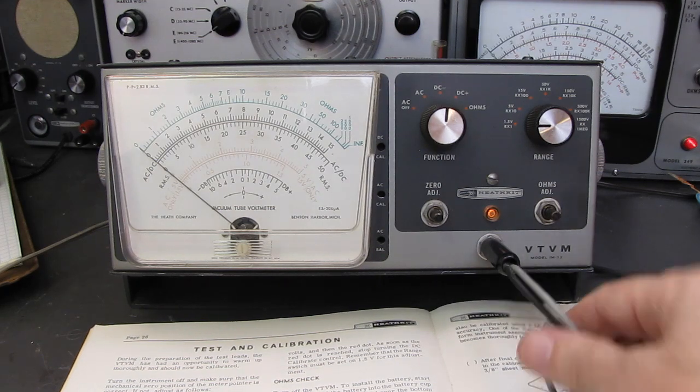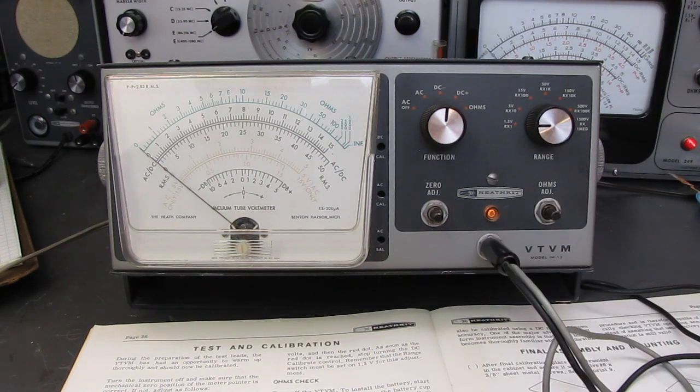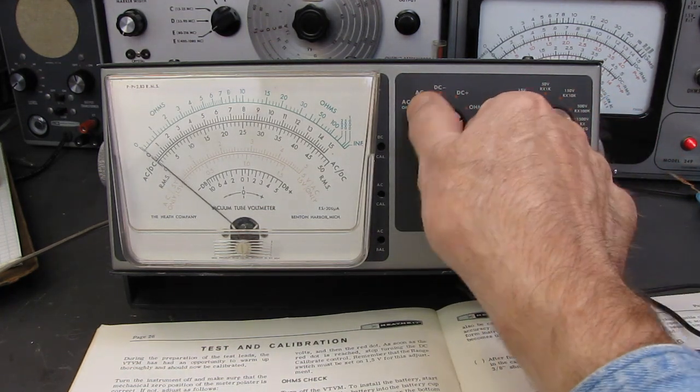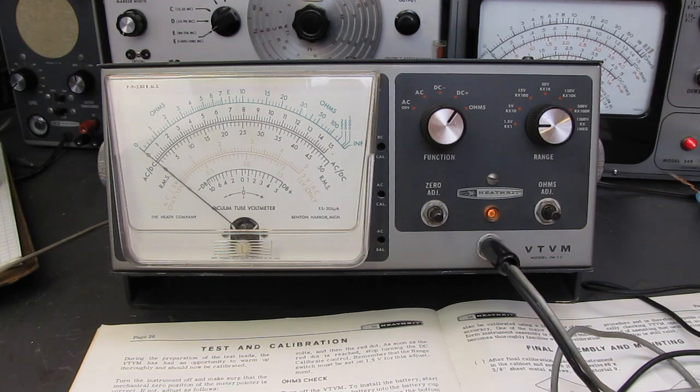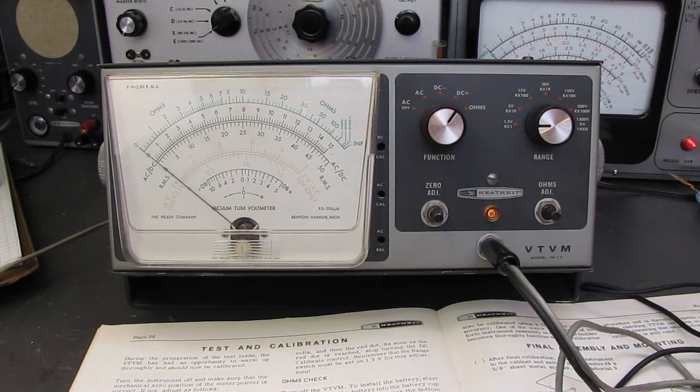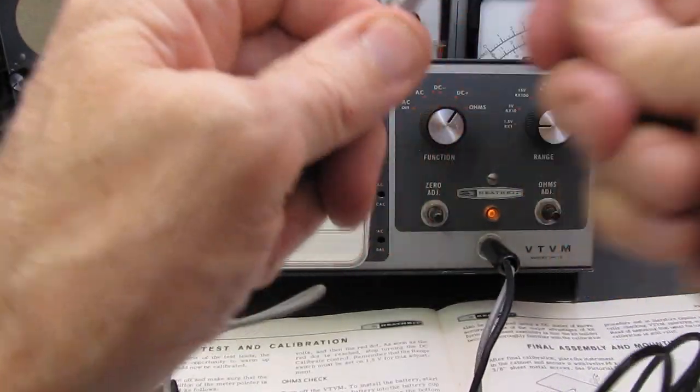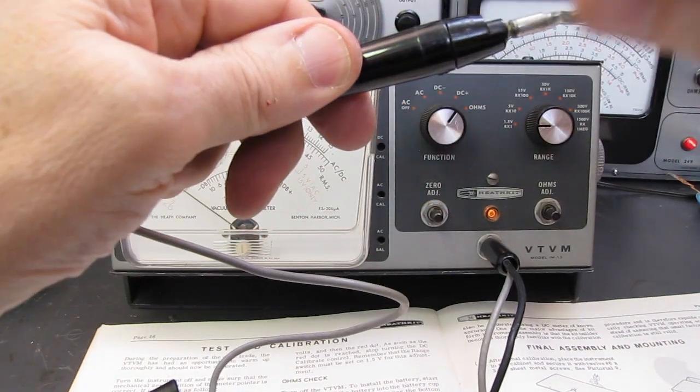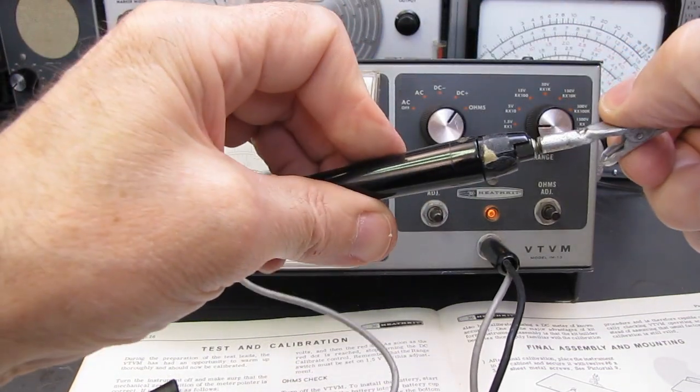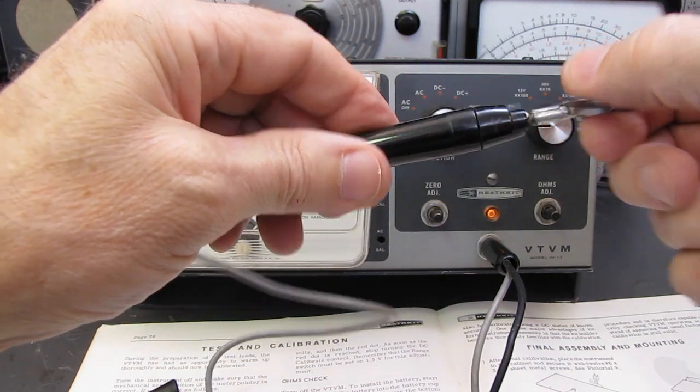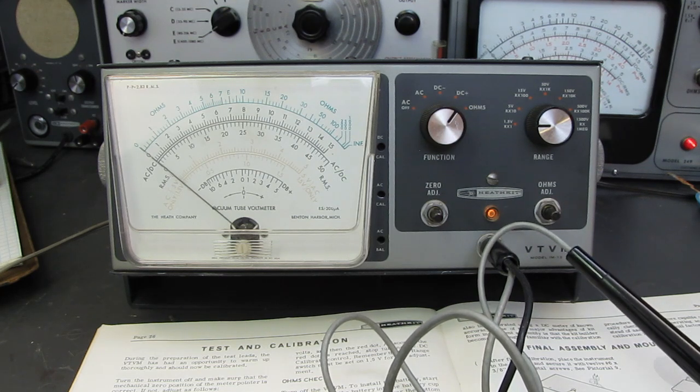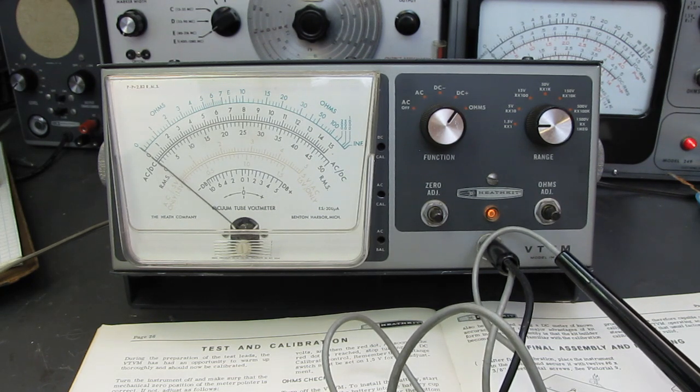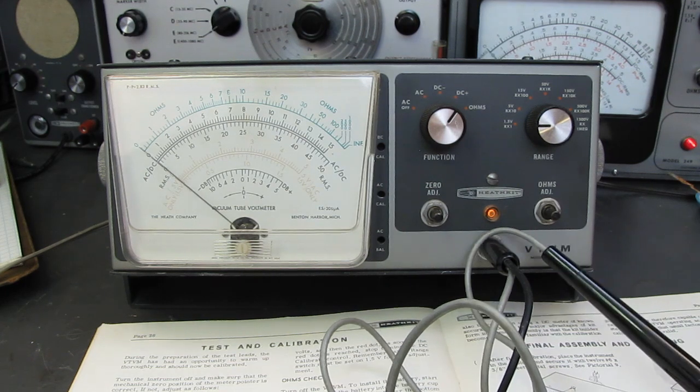If there's an appreciable zero shift of more than two divisions on the scale, it should be regarded as merely an indication that additional aging of the 12AU7 is required. And it says leaving the instrument turned on for a period of 48 hours or more is probably a good practice. DC calibrate. Insert the test lead into the phone plug. It's in there. I'm going to set the function switch to plus DC.